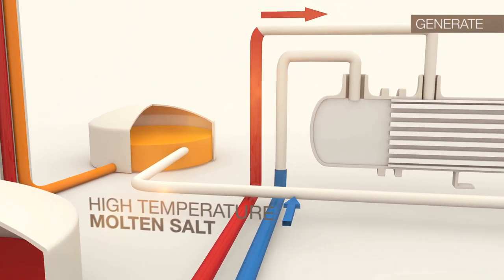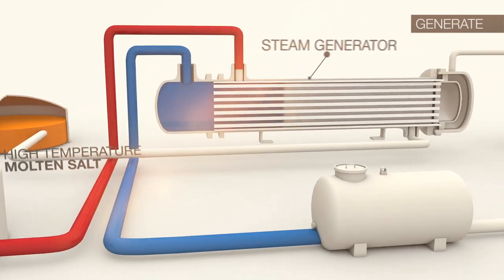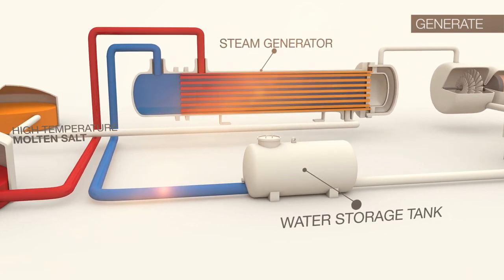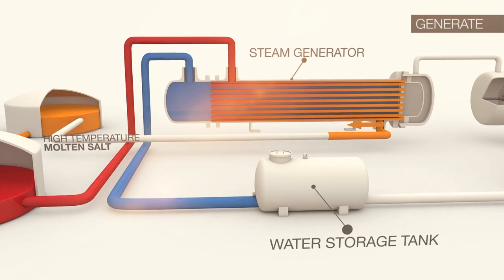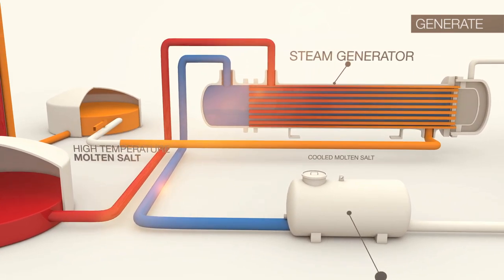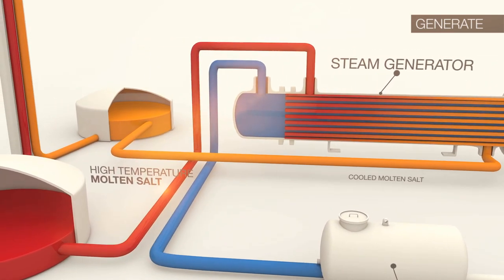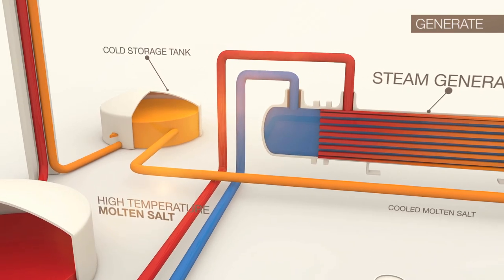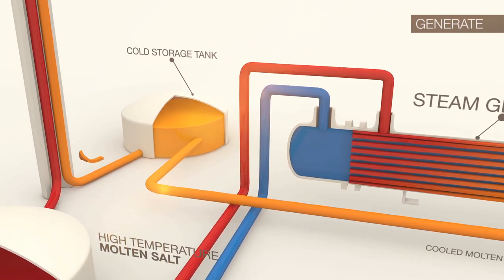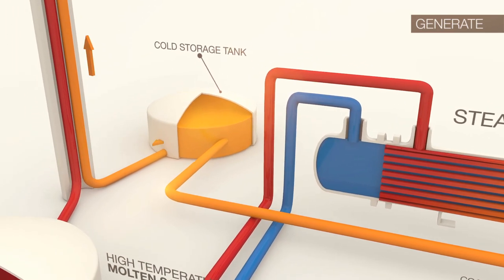the high temperature molten salt flows into the steam generator as water is piped in from the water storage tank to generate steam. Once the hot salt is used to create steam, the cooled molten salt is then piped back into the cold salt storage tank where it will then flow back up the receiver to be reheated as the process continues.